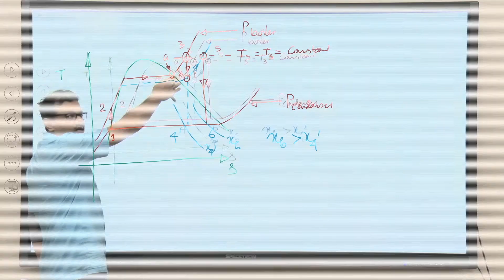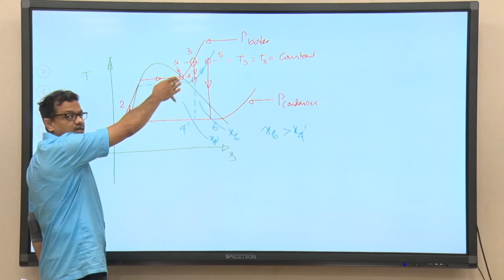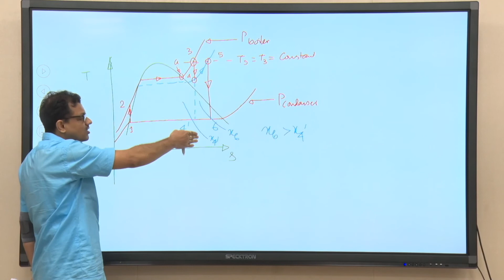So, this is point 6. If I allow the steam to expand isentropically from point 3 without reheating, then say if I give the name point 4 prime, try to understand, if we do not include this reheating stage and I allow steam to expand from point 3 isentropically, then the quality of the steam will be X4 prime. Now, quality of the steam is X6. So, definitely X6 is greater than X4 prime, right. So, though we are using high boiler pressure, we are still not going to compromise the quality of the steam, by how? By incorporating this reheating stage.